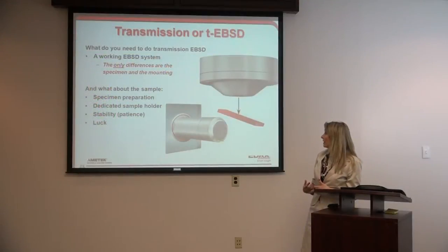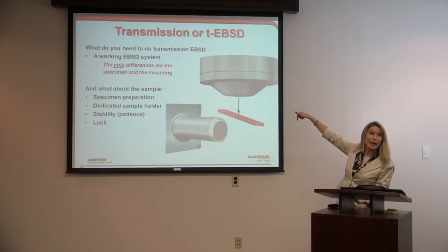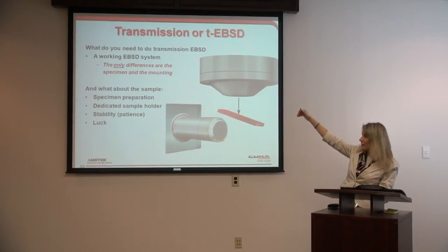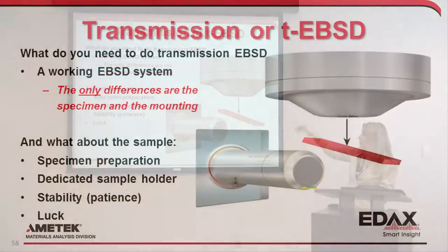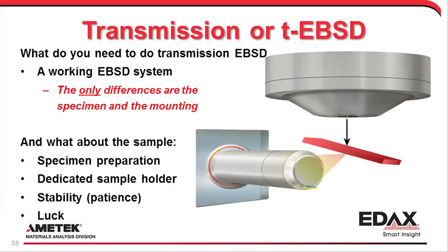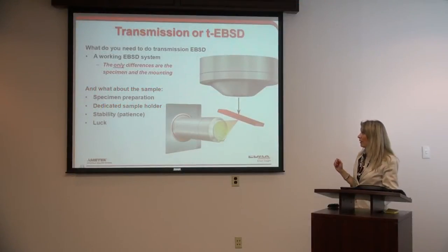With transmission EBSD, we open up a new world where we're using the electron beam to pass through the material. So a thin sample now, the electron beam being transmitted through and the diffraction being transmitted through and coming out the other side and being detected by the EBSD camera. All we need is a little bit different sample preparation.